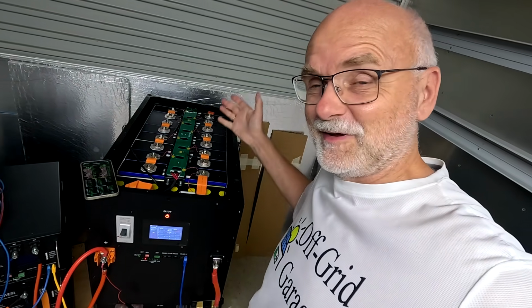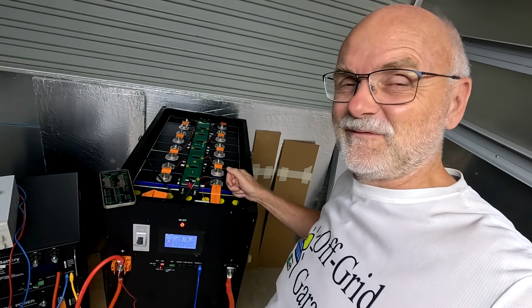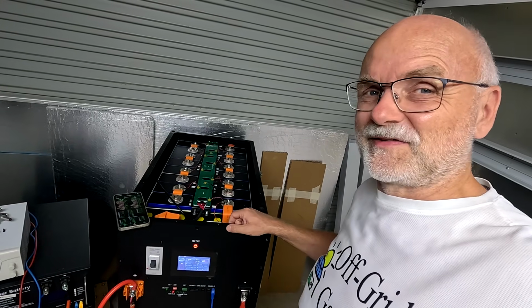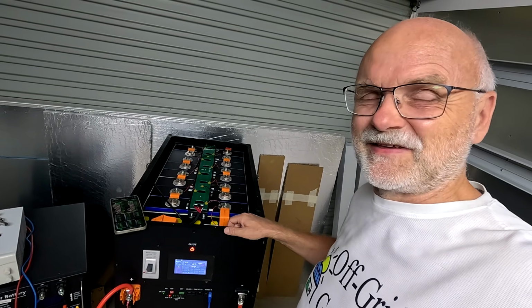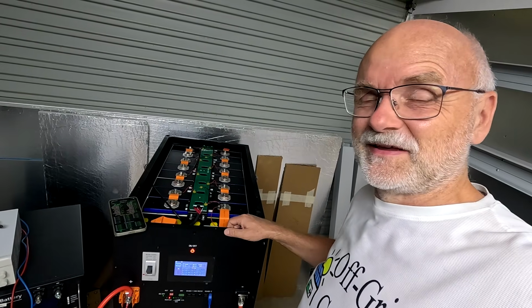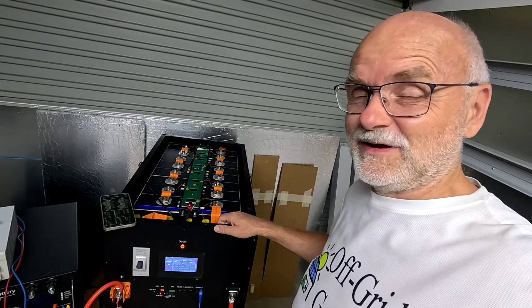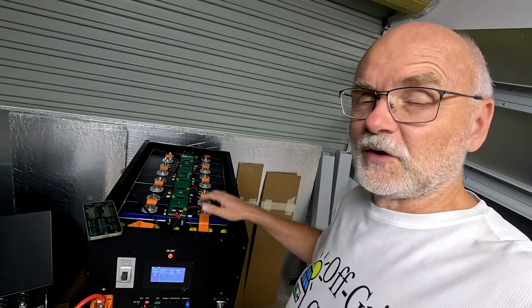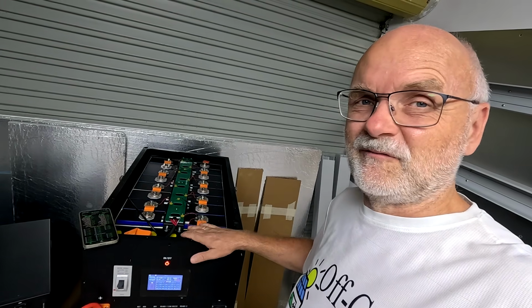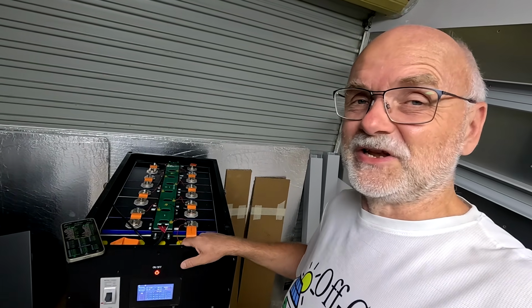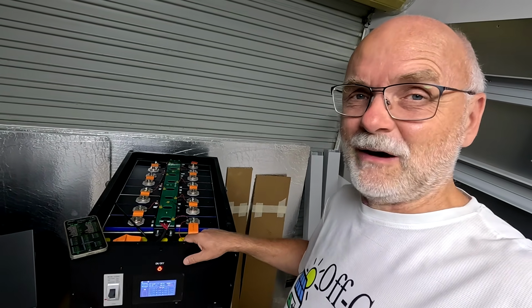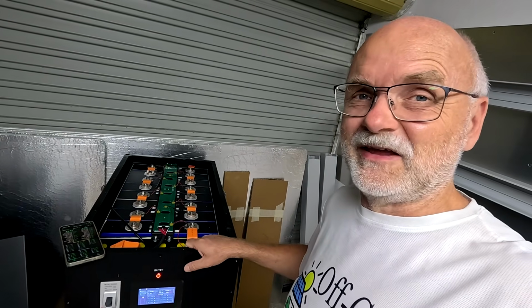Alright my friends, there you have it: the discharge test of the MB56 battery. 34 kilowatt hours, close to 660 ampere hours out of one battery. This is just one battery, so if you get two of them, you get close to 70 kilowatt hours, which is usually enough to power a single house for 2 or 3 days even without much solar coming in.